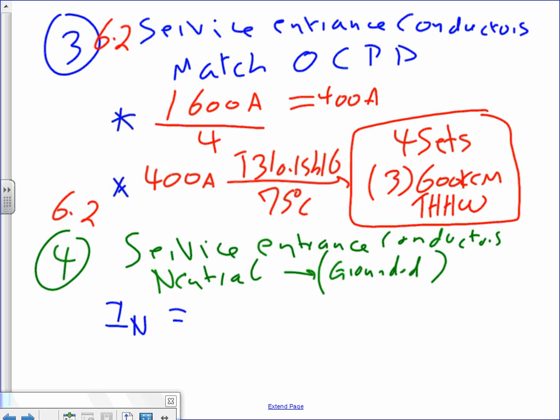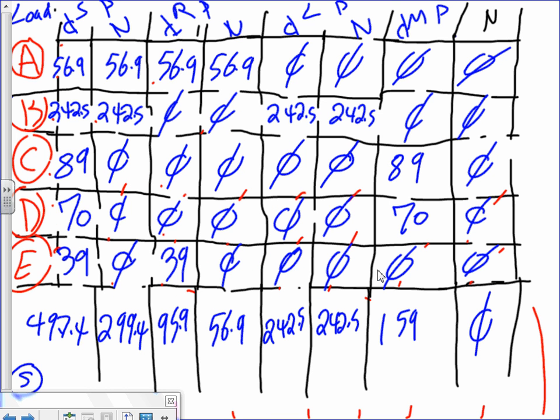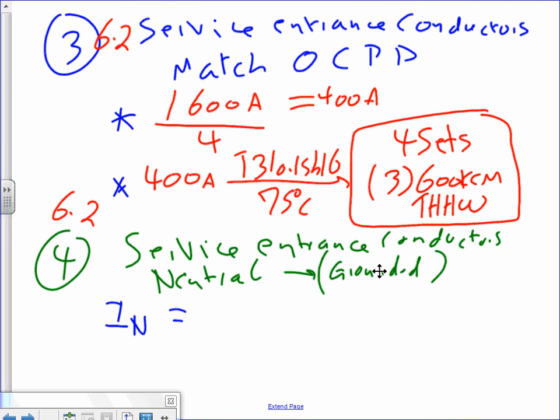Piece of cake. These are the phases. Now let's go size the neutral. If I want to take you guys back, do you remember the neutral load on the service was smaller than the phases, as expected, because things are balanced, which is always the reason why we use 3-phase. So you have 2 options. At Michaud and other firms, guys say, you know what, we're going to pull a full neutral. When you hear them saying full neutral, we're going to make it 3 conductors, 600 kcmil, and I'm going to make it 4. Call it a day. Done. You're good. Others, especially contractors, say, well, we can use the code to get a smaller conductor, cheaper installation. Did you guys see why they go smaller conductor, cheaper installation? And that's what we're going to do at the bottom.